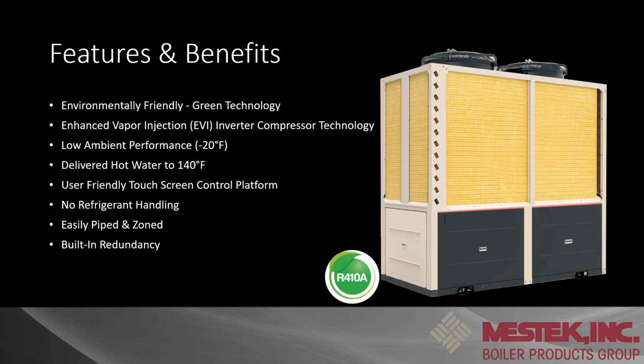So this product is designed for low ambient performance down to minus 20 degrees. And I'm going to show you some charts as we go through this that show, yes, it can heat at minus 20, but what kind of BTUs are you getting out, what type of water temperature you're getting out, and how do we design around that. Same thing with the delivered water temp. Yes, we can go up to 140 degree water with this, but it also is going to depend on the system, the environment around it, and how we achieve that. It has a user-friendly touch screen, so I'll show you a little bit on that.